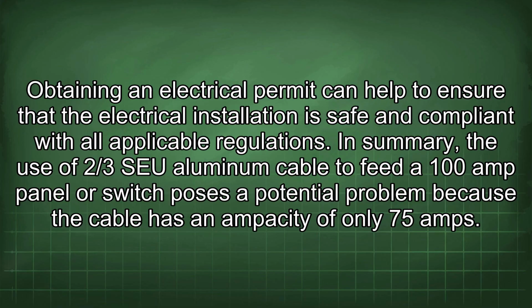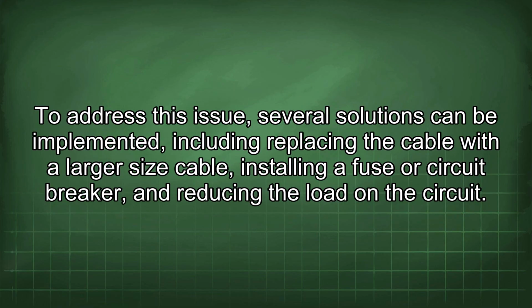In summary, the use of 2/3 SEU aluminum cable to feed a 100 amp panel switch poses a potential problem because the cable has an ampacity of only 75 amps. To address this issue, several solutions can be implemented, including replacing the cable with a larger size cable, installing a fuse or circuit breaker, and reducing the load on the circuit.